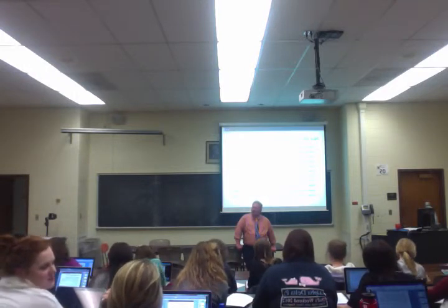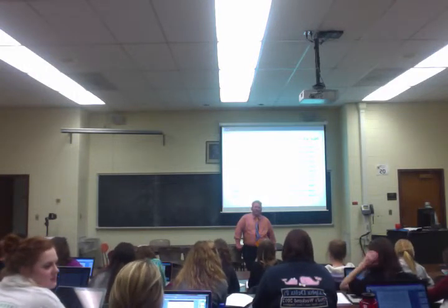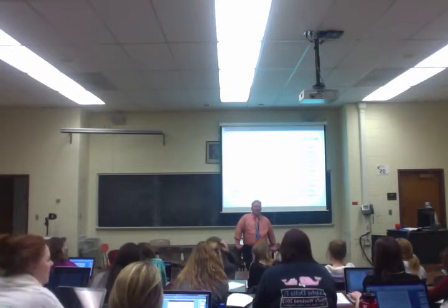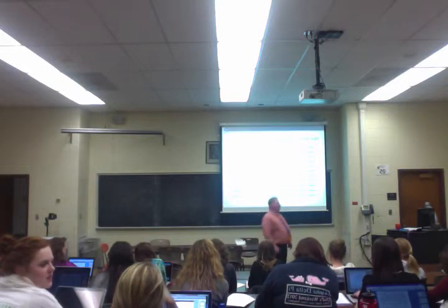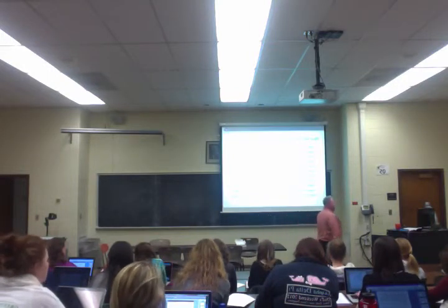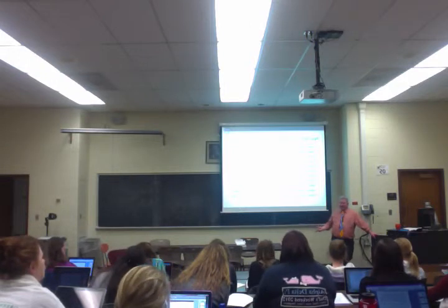But 9 times out of 10, I would guarantee you that there's probably some form of occlusion that, if you can clean it out, you will probably restore function to the hearing aid. And we will talk about hearing aid troubleshooting in the near future because you will be needing to learn how to do that. But know that not all hearing aids, as you saw, look exactly alike.